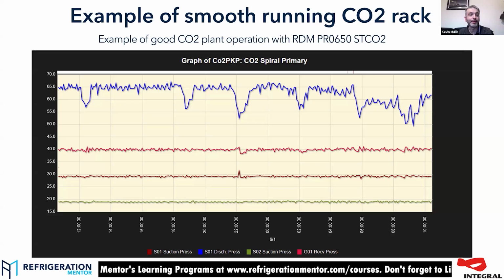And the load's stable. While there's product going in that plant, the load is pretty stable. So that gives you the opportunity to get the system running pretty smoothly. Not much we can do about the discharge pressure. That's related to ambient at the end of the day, which is your blue line there. You can see the times when they've had gaps in their production from the dips in the pressure. That's when they took load off the system.